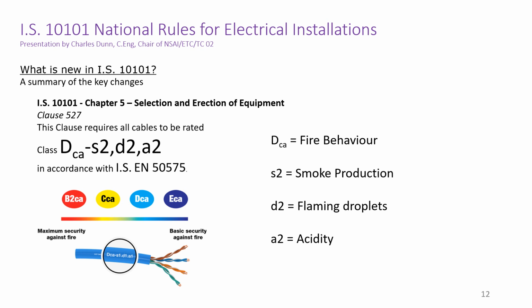The third part, D2, refers to the cable's tendency to emit burning droplets or particles. This relates to the habit of older PVC cables to release burning droplets of plastic onto the fireman working below. And the final part of the classification is A2, referring to the acidity and corrosiveness of emitted gas. This relates to the habit of older PVC cables to emit hydrochloric acid when they've been on fire for some time. Not very helpful to the fireman making his way along the corridor below where the cable has been installed.